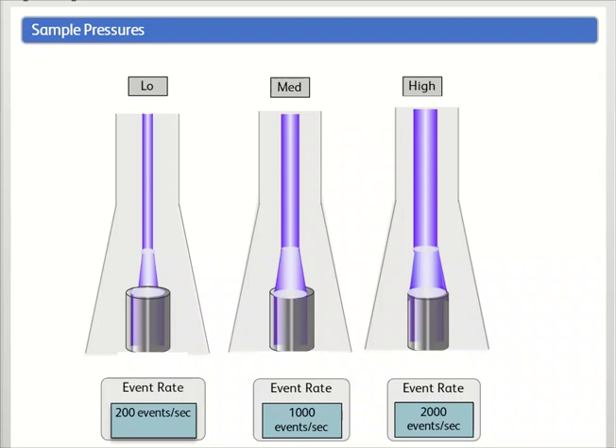When the sample pressure is low, the sample stream is narrow, and the event rate is low. When you increase the sample pressure, the sample stream widens and the event rate increases.